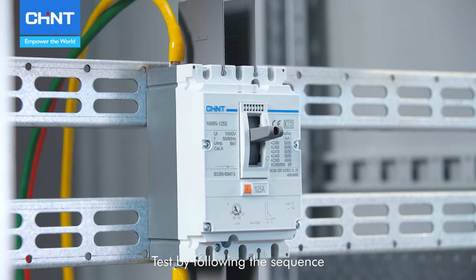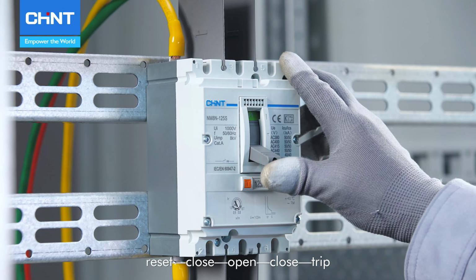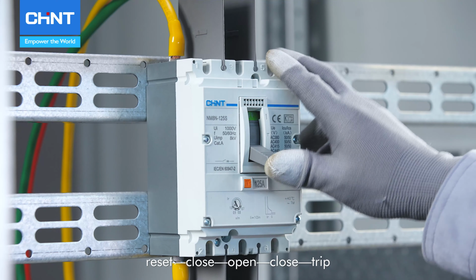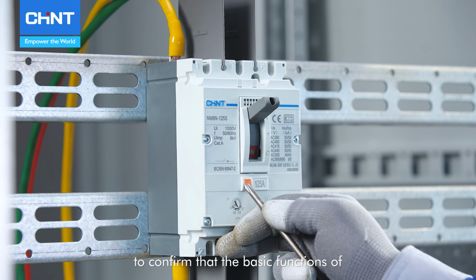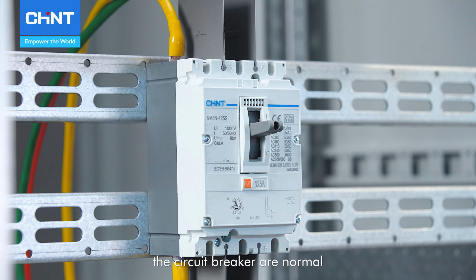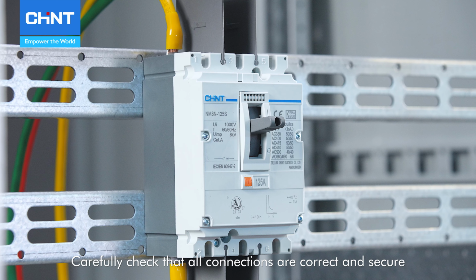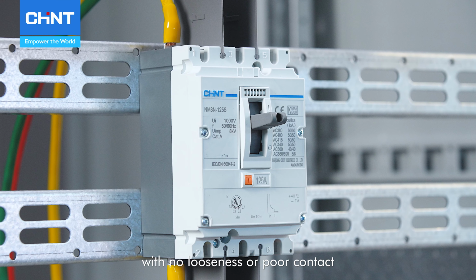Test by following the sequence: reset, close, open, close, trip, to confirm that the basic functions of the circuit breaker are normal. Carefully check that all connections are correct and secure, with no looseness or poor contact.